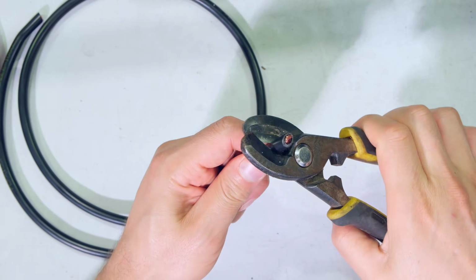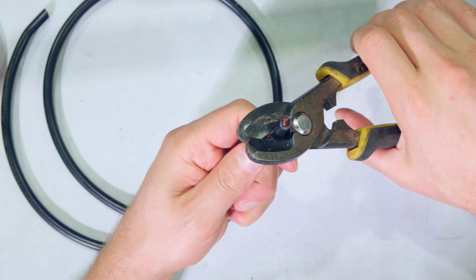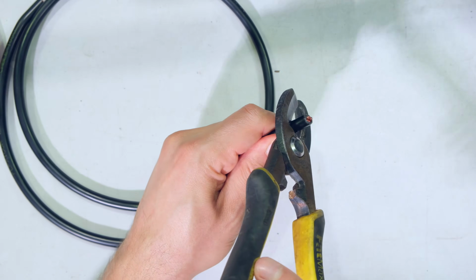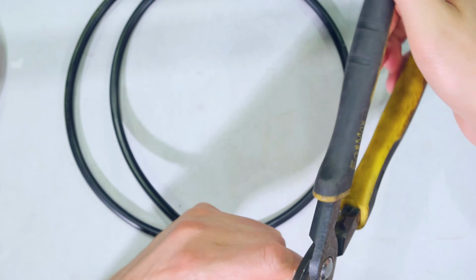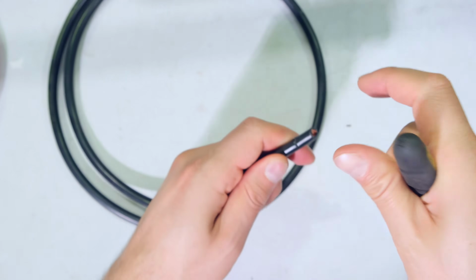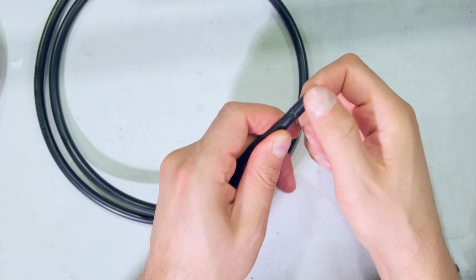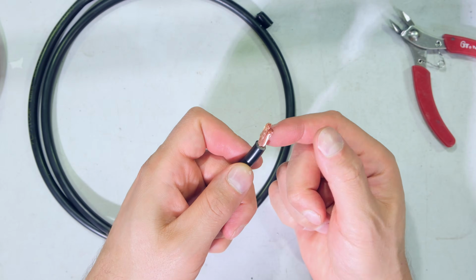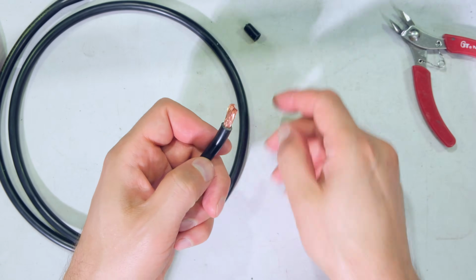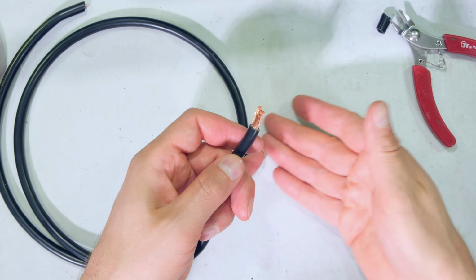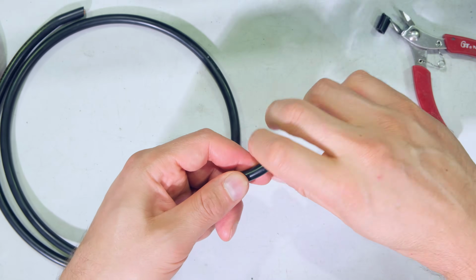I'm taking my side cutters here, and I'm not cutting into the copper. What I'm doing is I've closed the mouth a little bit, and I'm just going around in a circle here to make sure that I've cut through just the sheath. There it is, and there it comes off. Notice that none of these copper strands came off. If I did this incorrectly, you would see copper strands on the table here. There's no strands on the table.